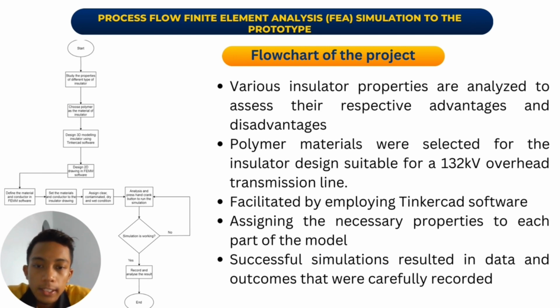Polymer materials were selected for the insulator design suitable for 132 kV overhead transmission lines. The design process was facilitated by employing Tinkercad software, which allowed for creating a 3D model of the insulator. The next step involved simulating the 3D model using FEMM, beginning with assigning the necessary properties to each part of the model.